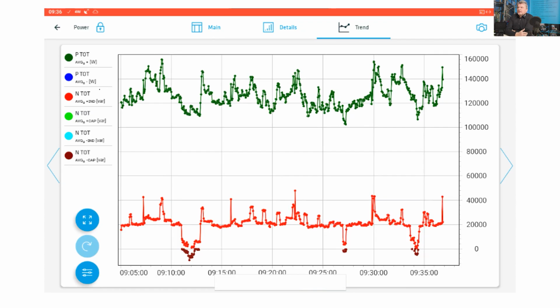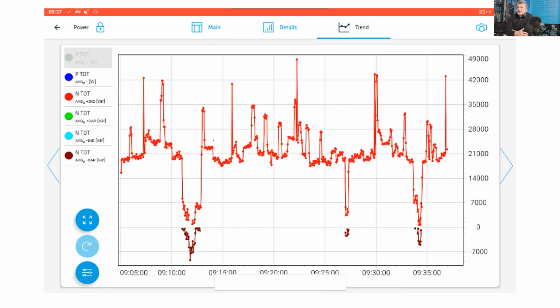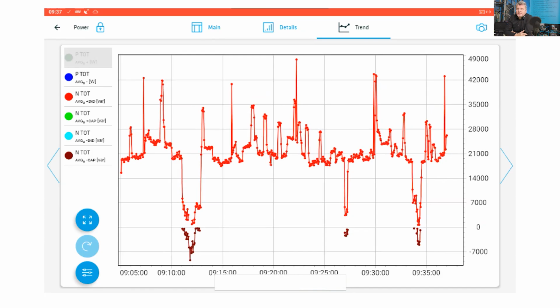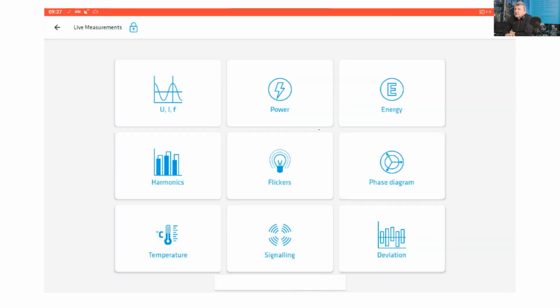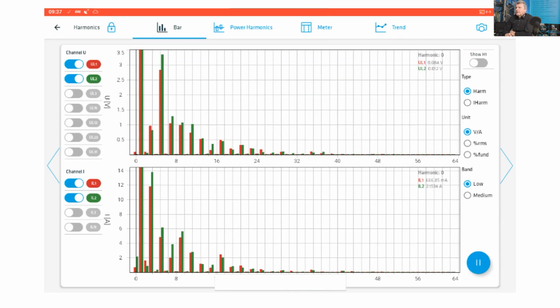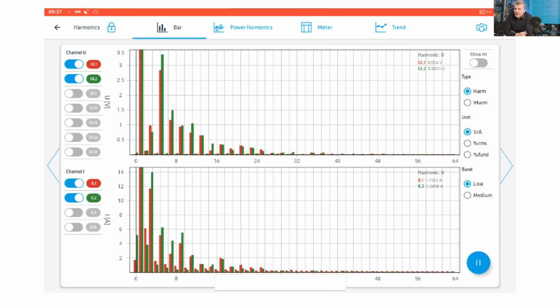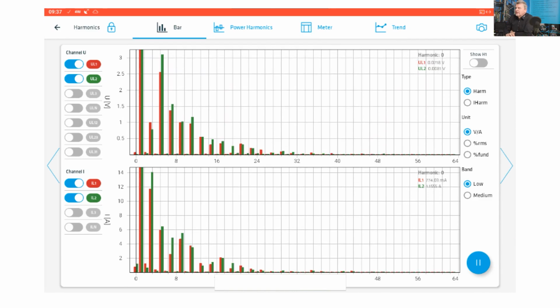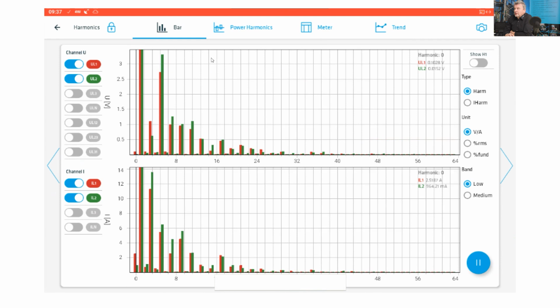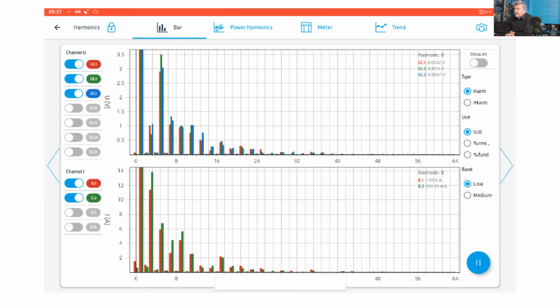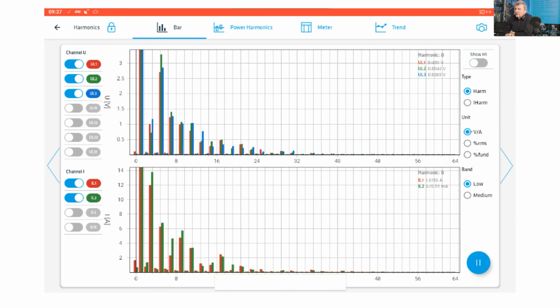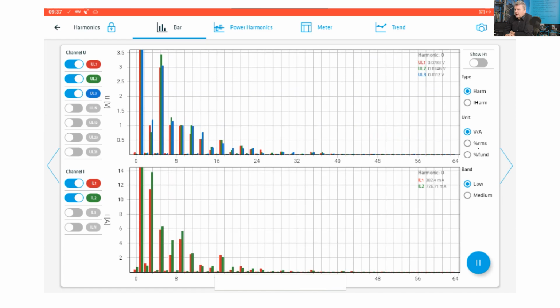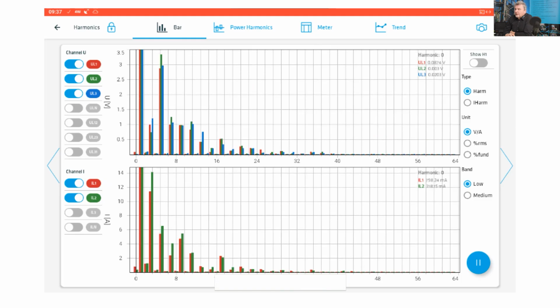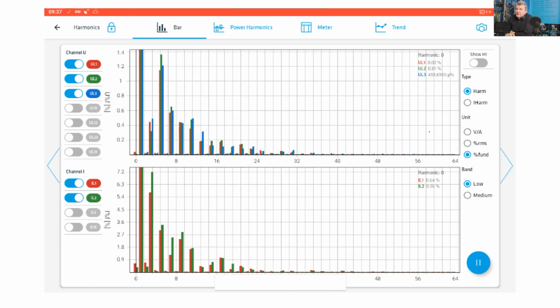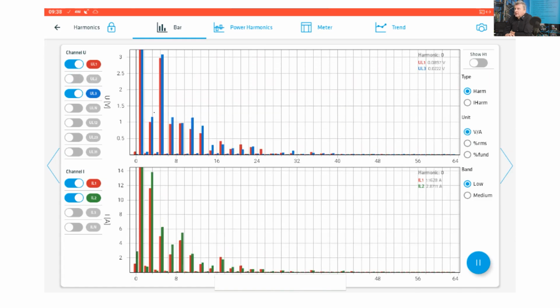Normally you will select one view, which is then saved automatically. It will automatically appear the next time. So you just stop on the harmonics view. For the harmonics, as I mentioned, we are measuring up to the 63rd harmonic for voltage and current, and also interharmonics. Harmonics are presented in specific views, like absolute value, or related to the RMS or fundamental. So you can monitor a specific phase separately. You can stop it if you need to analyze.